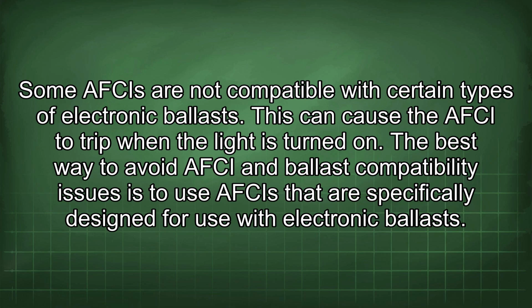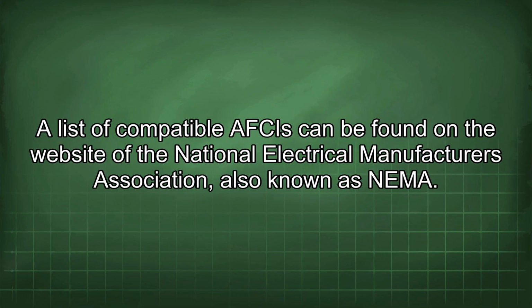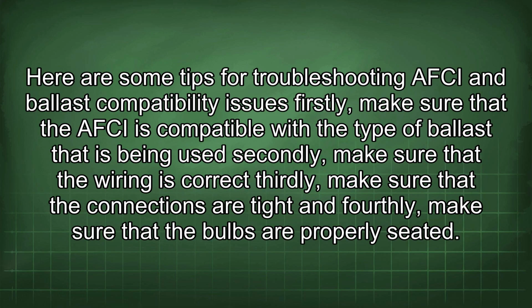The best way to avoid AFCI and ballast compatibility issues is to use AFCIs that are specifically designed for use with electronic ballasts. A list of compatible AFCIs can be found on the website of the National Electrical Manufacturers Association, also known as NEMA. Here are some tips for troubleshooting AFCI and ballast compatibility issues.